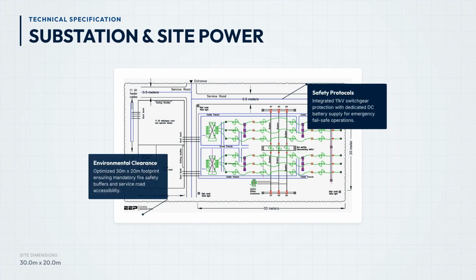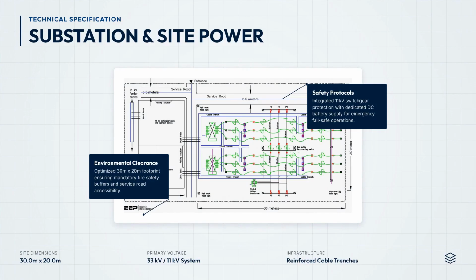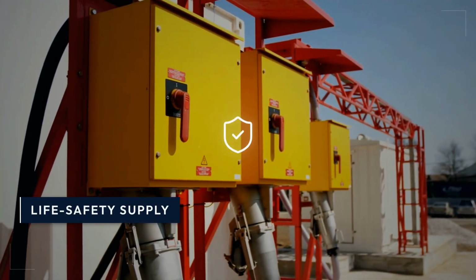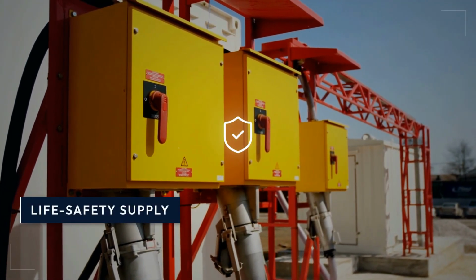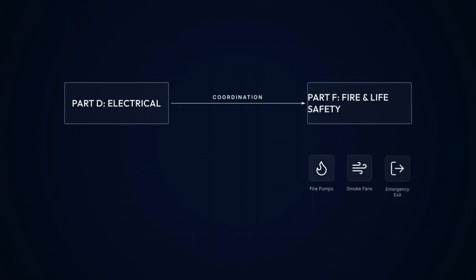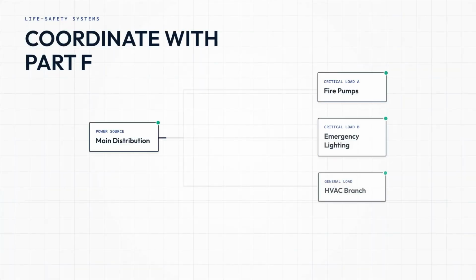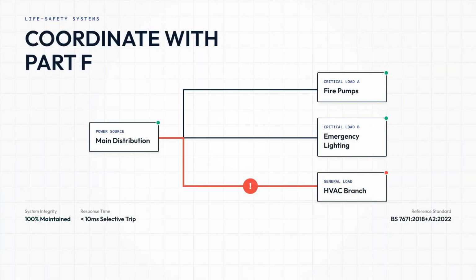A few more: substation and generating set location and layout, their environmental and safety provisions have been updated. Electrical installations for construction and demolition sites have been reviewed, so temporary site power is safer. And the electrical supply for life safety services has been reviewed - that one you must coordinate with Part F, Fire and Life Safety. Your fire pumps, your smoke fans, your emergency lighting all depend on that supply staying alive.